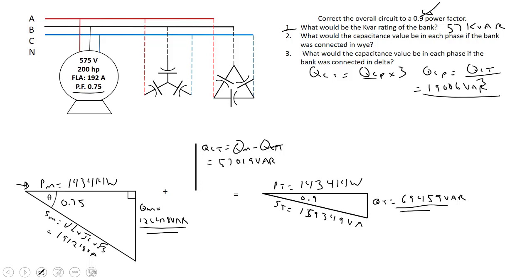That's the same whether it's Y or Delta. Now our new formula is XC equals our phase voltage squared divided by the VARs per phase from our capacitor bank or the QC per phase.